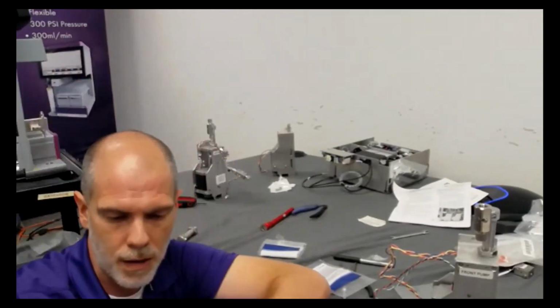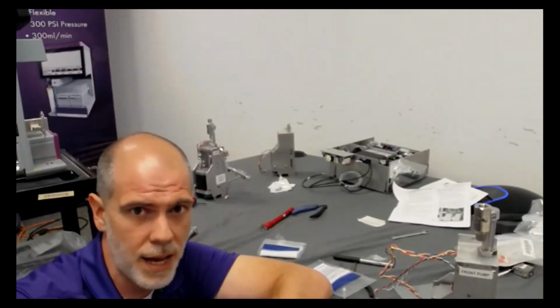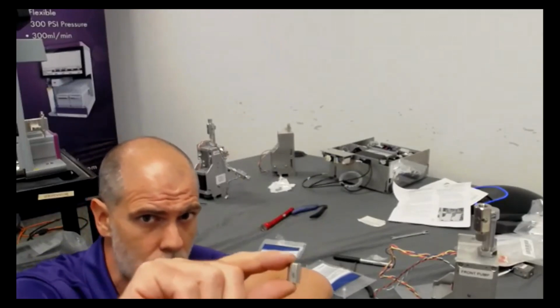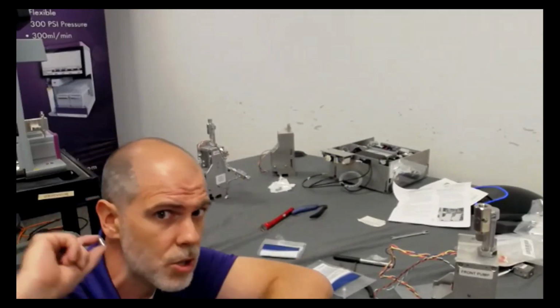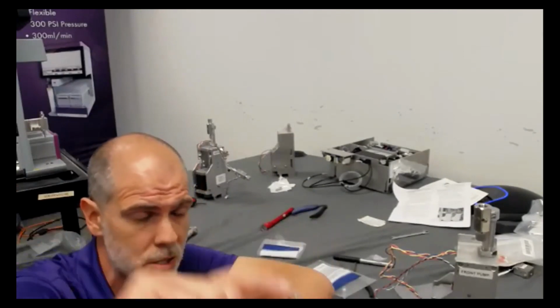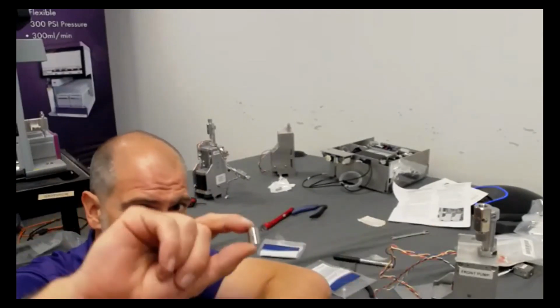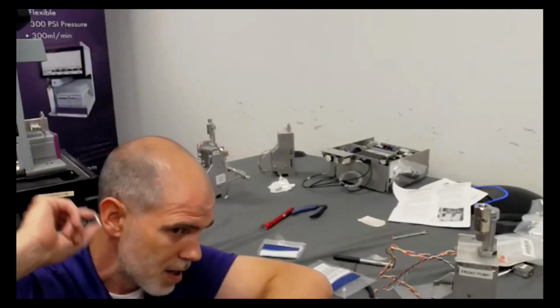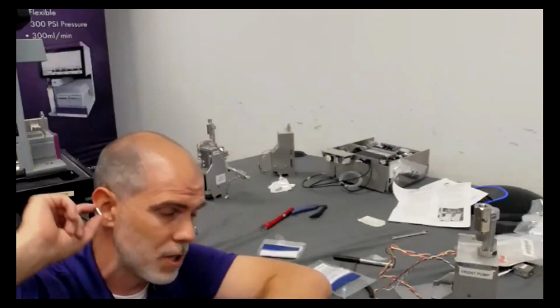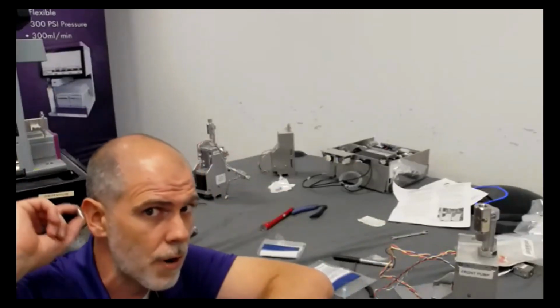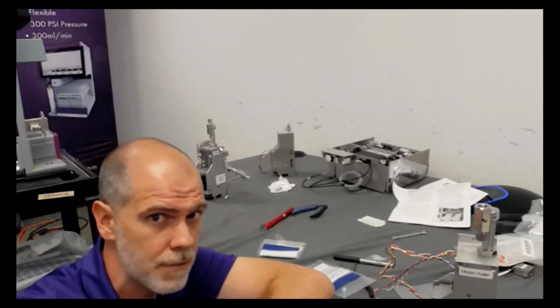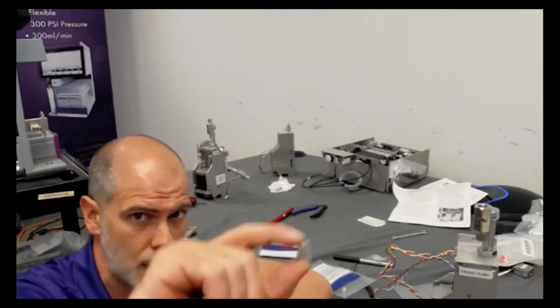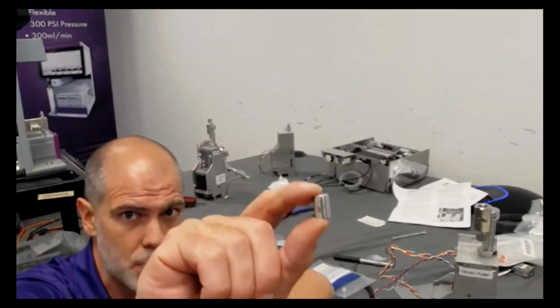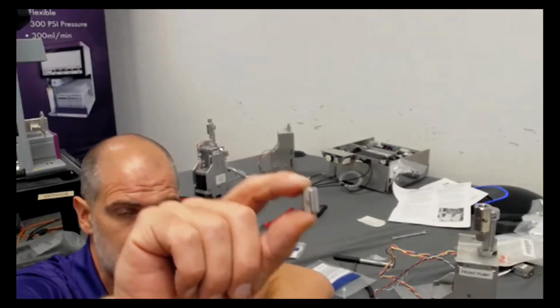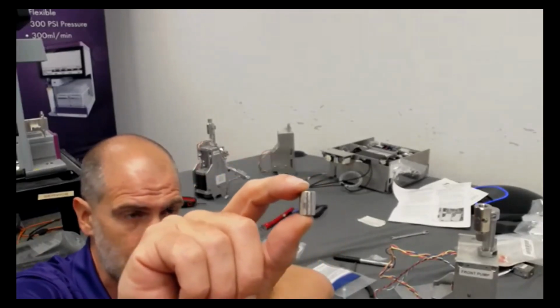All right. You don't always even have to take out your check valves. If you know they're new within the last year, you can leave them alone if you're getting good performance. But for a PM, sometimes it's a good idea to take these out. At least make sure one of them rattles. If you need to, you soak them. If they're not rattling and you know you have issues with check valves anyway, take them out and sonicate them for 10 to 20 minutes in some kind of strong solvent, okay?